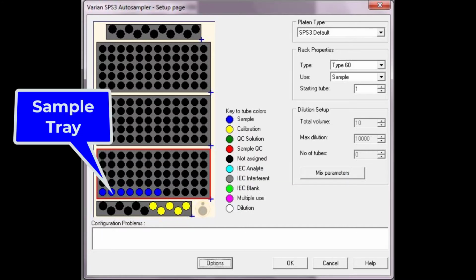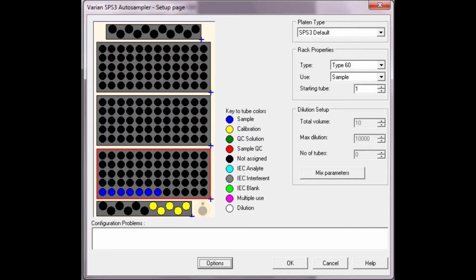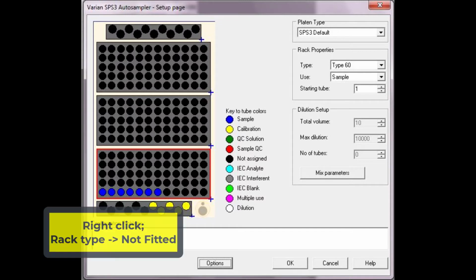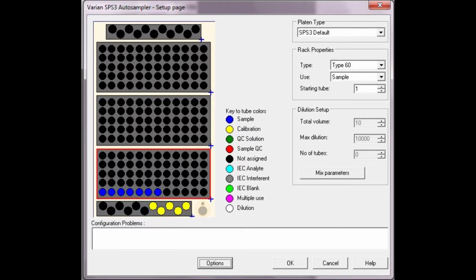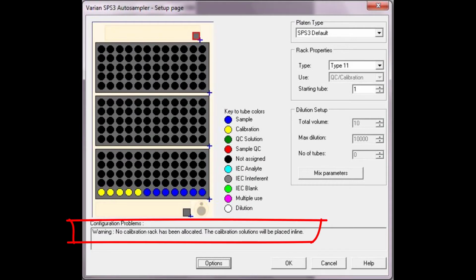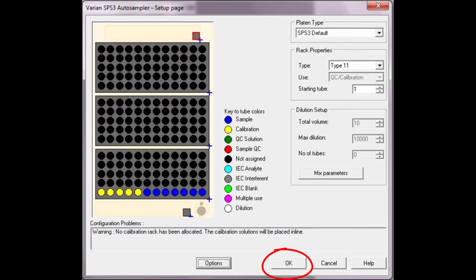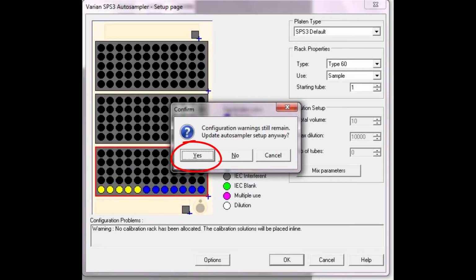We don't have the small standard trays, so we need to move the calibrations to the holder with the samples. To do this, right-click on the calibration tube tray on the bottom and select Rack Type Not Fitted. Then do the same for the top tray. A warning will appear at the bottom of the screen because we no longer have a designated tray for calibrations. Since we are not in an industry lab, this is fine. Press OK here, then press Yes when a reminder of this warning pops up.